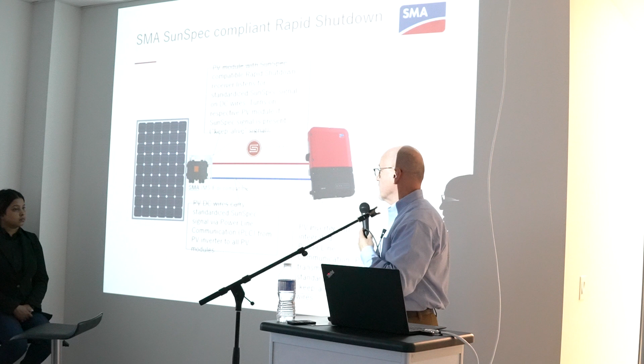The way SunSpec Rapid Shutdown works, as long as you have AC power at the inverter, a keep-alive signal is being transmitted over the DC conductors using an old technology called power line communications. That signaling type is used in a lot of different industries for different things, but the keep-alive signal is unique to this.